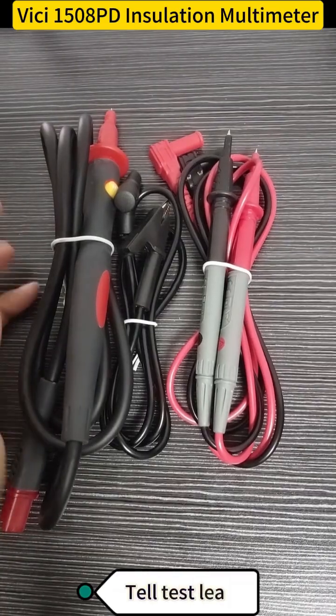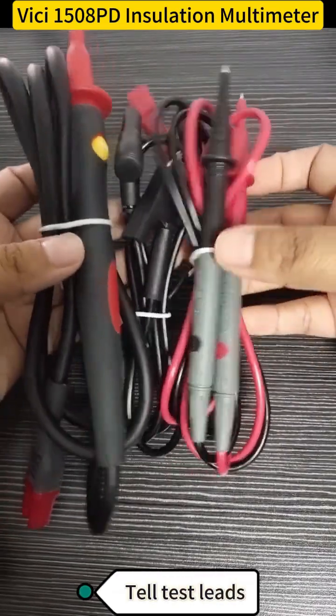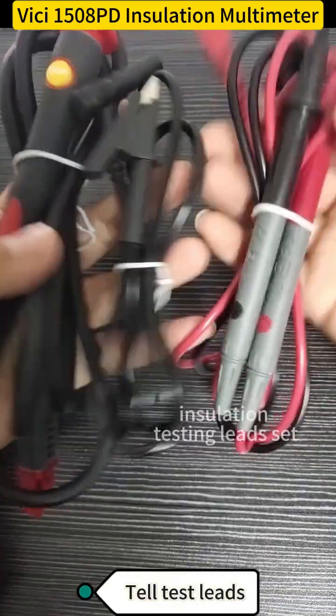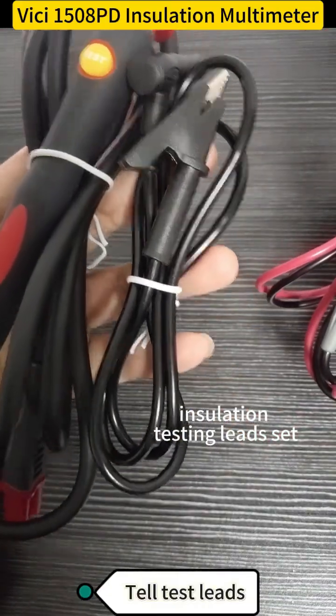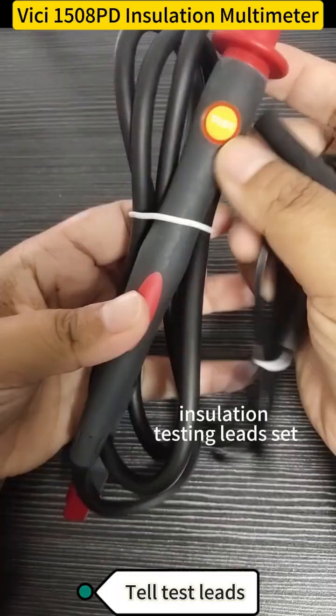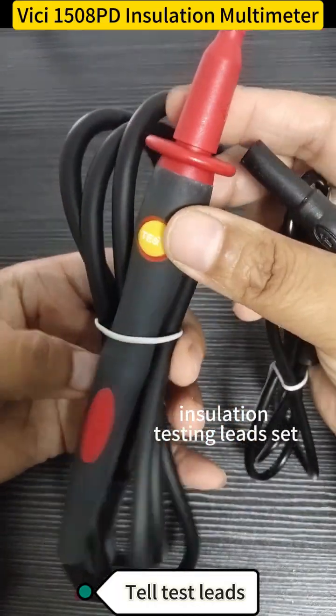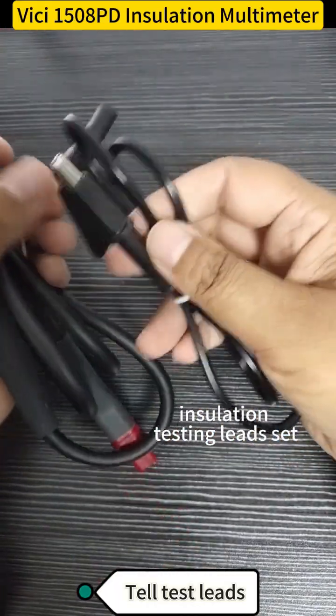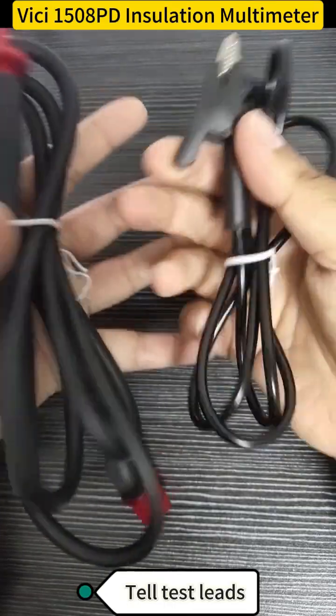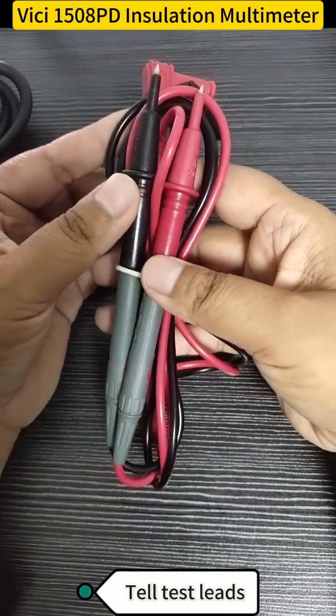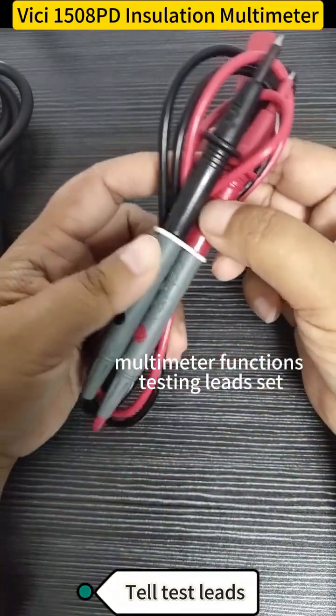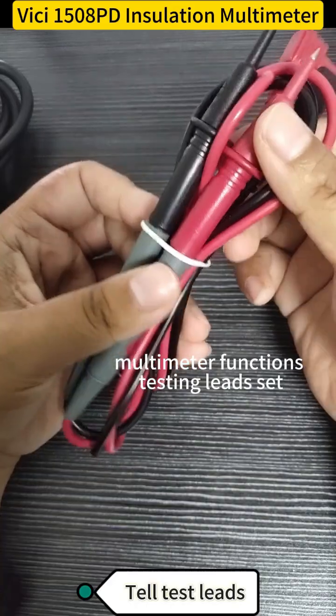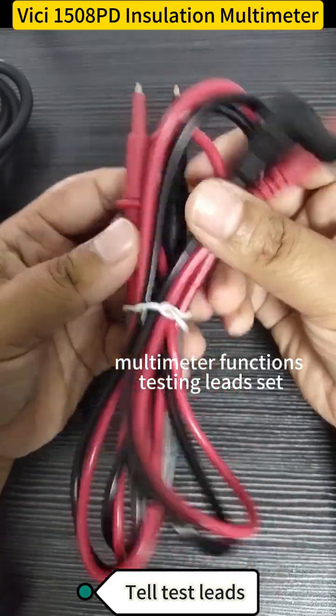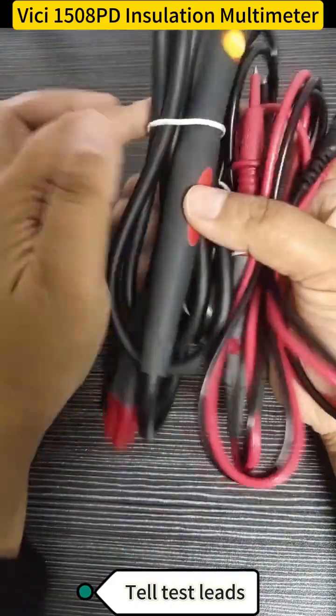First up, let's take the standard test leads apart. Do not mix them up. One set is for the insulation testing. It includes a remote test lead like this one, and another one is the alligator clip. This is for the insulation test, and this pair is for the multimeter work, like measuring voltage, resistance, and capacitance. Keep them separate. Now let's go over how to plug them in correctly.